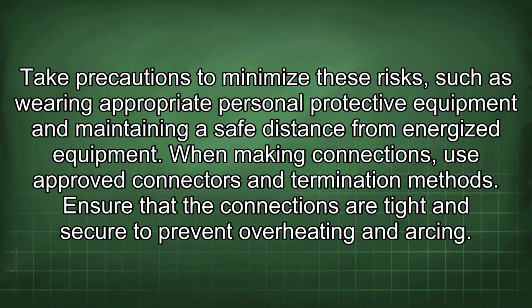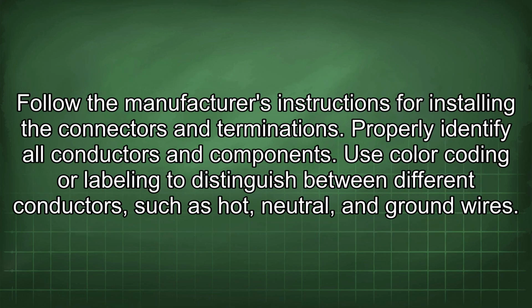equipment. When making connections, use approved connectors and termination methods. Ensure that the connections are tight and secure to prevent overheating and arcing. Follow the manufacturer's instructions for installing the connectors and terminations. Properly identify all conductors and components. Use color coding or labeling to distinguish between different conductors, such as hot, neutral, and ground wires.